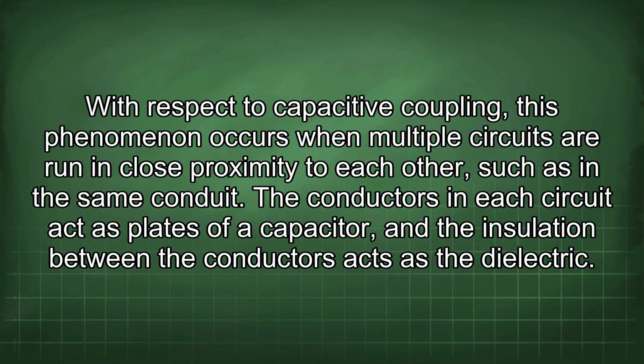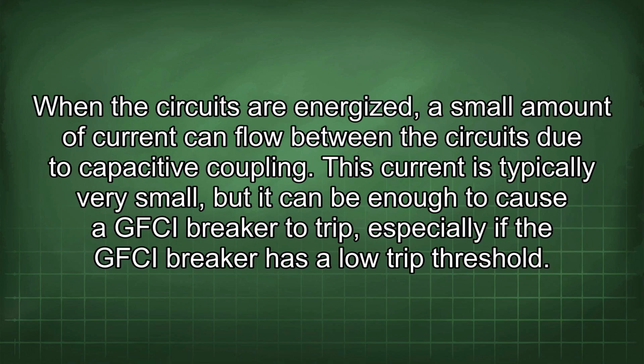With respect to capacitive coupling, this phenomenon occurs when multiple circuits are run in close proximity to each other, such as in the same conduit. The conductors in each circuit act as plates of a capacitor, and the insulation between the conductors acts as a dielectric. When the circuits are energized, a small amount of current can flow between the circuits due to capacitive coupling. This current is typically very small, but it can be enough to cause a GFCI breaker to trip, especially if the GFCI breaker has a low trip threshold.